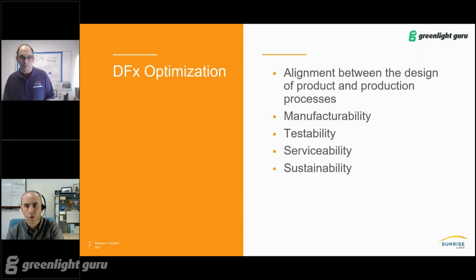Exactly. You and I have had conversations about something as simple as ingress protection for a particular product, and decisions made about whether we're going to glue parts together, use gasketing and hardware, or use ultrasonic welding. That will have an effect on the ability to service that product later on, whether it's out in the field or troubleshooting a product that's failed at the system level.